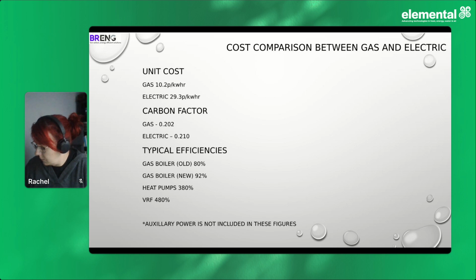Then we start to look at the typical efficiencies of heat generating equipment. An old boiler typically has an efficiency of around 80%, and new boilers are obviously more highly efficient. Then you get into heat pumps. That 380% figure is an efficiency factor used when the heat pump is being used at its best, most controlled delivery of hot water. What you'll find is people try to use heat pumps like boilers, so you have to be careful, because that 380% can actually drop to only 200%, which isn't of any benefit to anybody in a school. Then there's the next level of heat pumps, called VRF, which has an even higher efficiency.